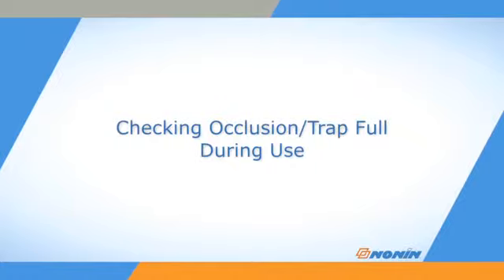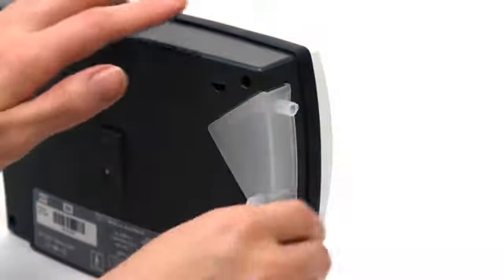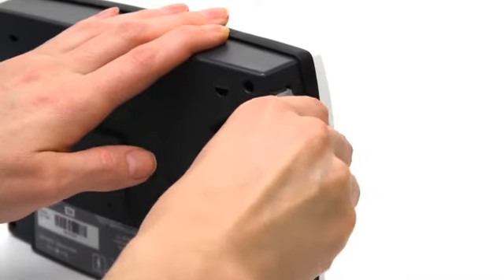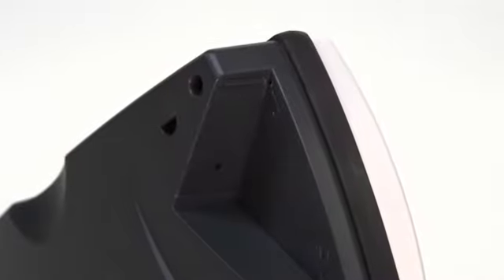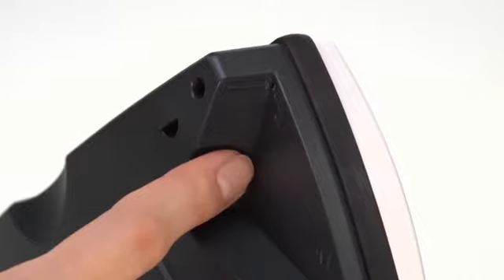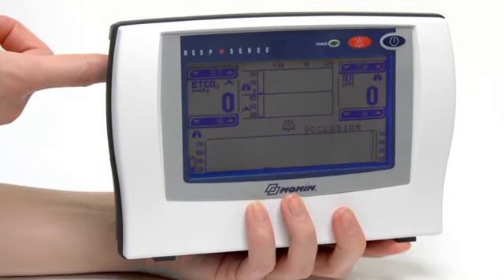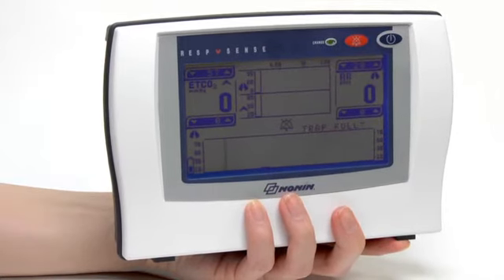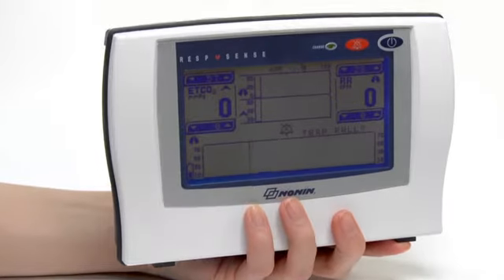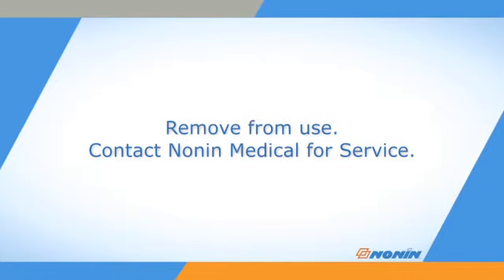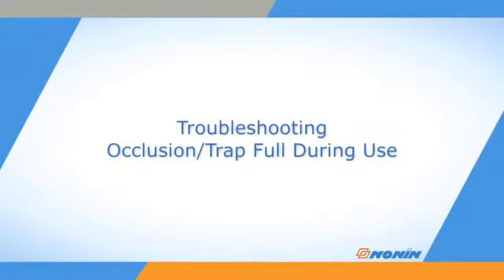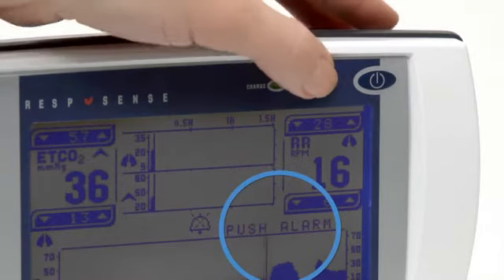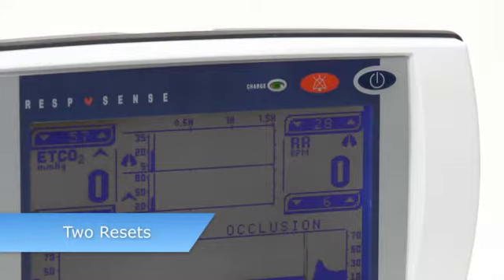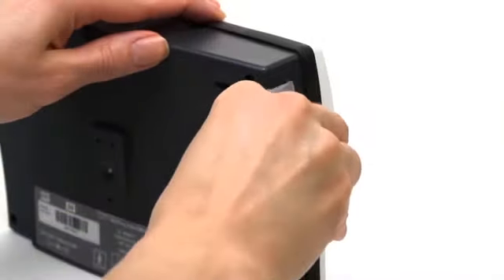You can periodically check the unit's occlusion and trap full alarm functions. With the unit running, with no cannula attached, remove the filter and moisture trap assembly. Press your finger over the small hole in the filter and trap slot. Within 5 to 10 seconds, you should first see the occlusion display and then the trap full push alarm display. Press the Alarm Reset button to clear the alarm. If these do not occur, remove the monitor from service and contact NONIN Medical for service. If the trap full push alarm occurs during use, press the Alarm Reset button. If the monitor continues to occlude after 2 alarm resets, occlusion will display, followed by the trap full push alarm. Change the cannula or filter.